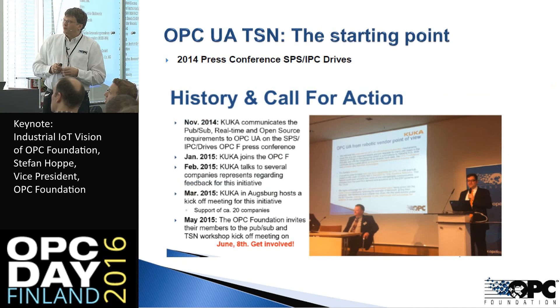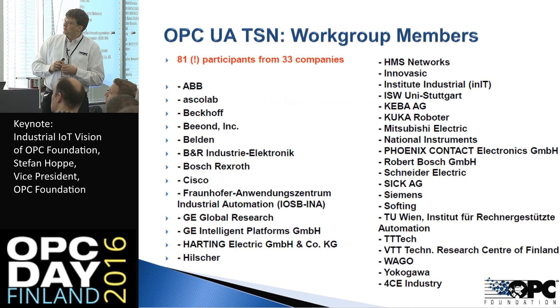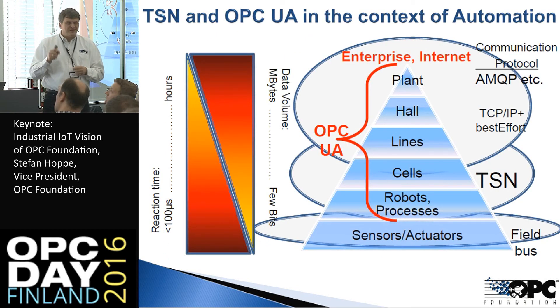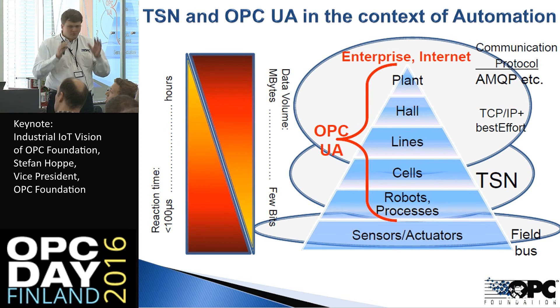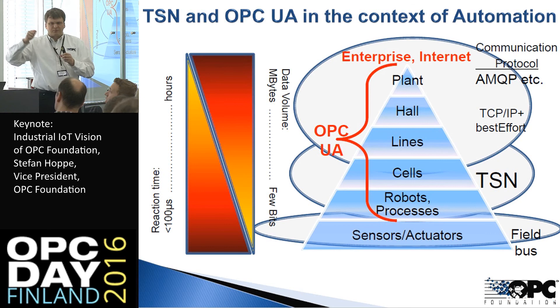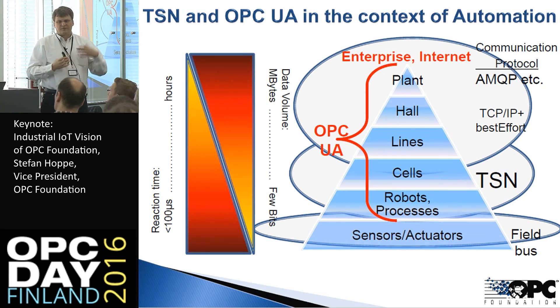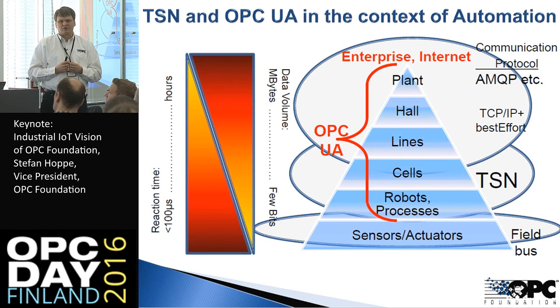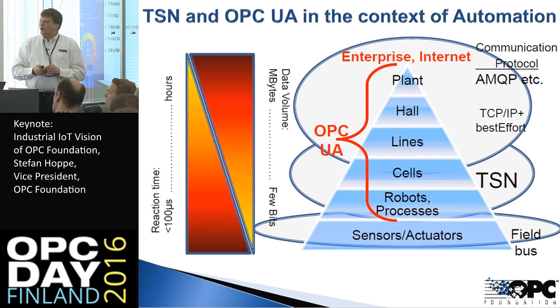I already talked about OPC UA and TSN. There was a slight mismatch — 81 participants are in that group. OPC UA and TSN is definitely not reducing or fighting against fieldbus systems. Don't start thinking about that. Fieldbus systems are optimized for bit and byte transport, for motion control in highly deterministic microsecond areas. But think about all these services — between the RFID reader and the MES system or PLC — today we cannot calculate the time for that network communication. This is exactly where TSN helps to reduce the load on the wire.